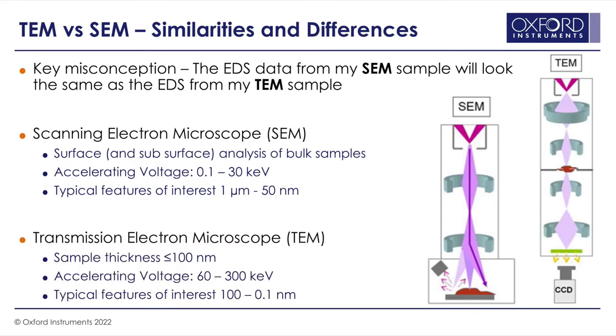Comparing that to a TEM, a transmission electron microscope — the ray diagrams look very similar, it just looks like a TEM is bigger, which is true, it's at least twice the size. Our samples have to be electron transparent, meaning less than 100 nanometers thick. A TEM will typically operate at 60 kV up to 300 kV, with the biggest machines in the world being over a thousand kV. For features of interest, we're now talking nanometers — most TEM samples will be looking at features sub 100 nanometers, all the way down to angstroms and atomic resolution.